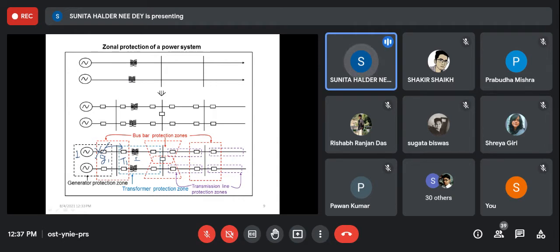So in this way, there is a concept of primary protection and backup protection. And always the protection zones are overlapping. If this is the transmission line protection zone, this is the bus bar protection zone. So this transmission line protection zone is also supplying protection to the bus bar. So they are overlapping to ensure better protection scheme.